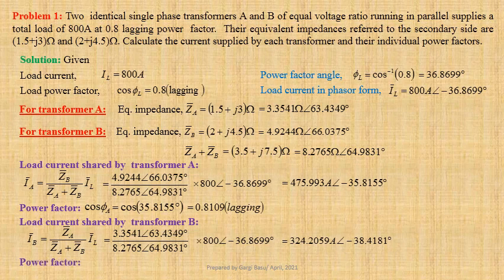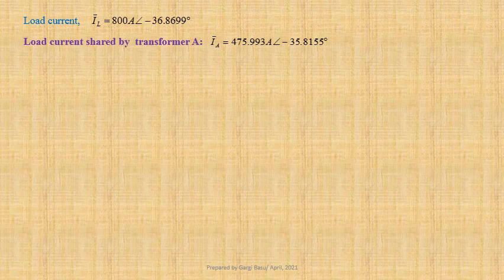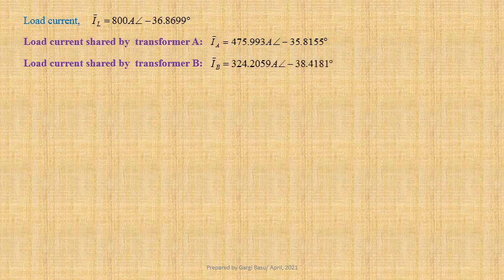Operating power factor of transformer B, cos phi B, equals cos of 38.4181 degree, that gives us 0.7835 lagging. Load current IL equals 800 ampere at an angle minus 36.8699 degree. Load current shared by transformer A: IA equals 475.993 ampere at an angle minus 35.8155 degree. Load current shared by transformer B: IB equals 324.2059 ampere at an angle minus 38.4181 degree.